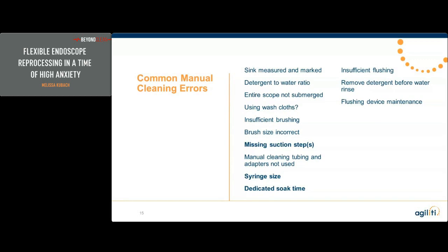I still see the number one missing step is the suction step with the suction adapter for one of the leading models, and this has been the most popular step to skip for many, many years. But I do see this improving with some of the new automated flushing units that include that step. You don't need the suction adapter anymore, which makes it a lot more appealing because you don't have to have another item to either high-level disinfect manually or sterilize. This is really getting this step put back into the process because you cannot skip it underneath the programming. So that is really good.